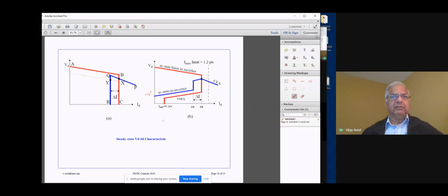This causes high voltage stresses related with the current extinction, and in order to protect the valves, we impose this current limit over there. So this is now the characteristic for an HVDC transmission system with a modified characteristic. Okay. So these modifications help to protect the valves, help to protect the DC transmission system, and they are a very useful part of the transmission system.